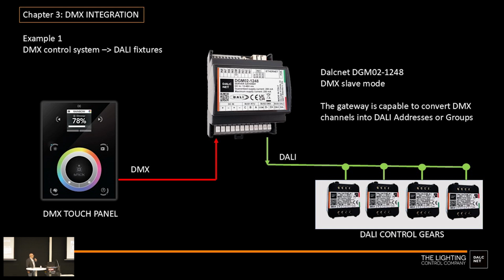Another interesting thing is that I can create an offset between the DMX channels and the DALI channels. This offset is interesting and not so common. Why? Because on the touch panel, on the DMX side, I have 512 channels, while on DALI I have only 64. So one option is to connect on the DMX side a lot of different converters that control up to 8 different DALI buses. But to do that, I need to create an offset so the DALI buses and DMX channels don't overlap.